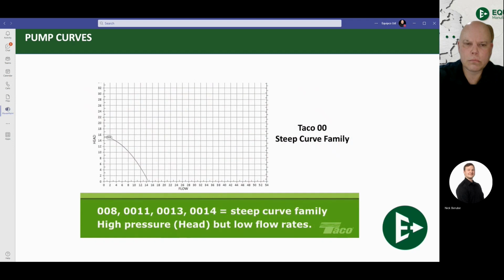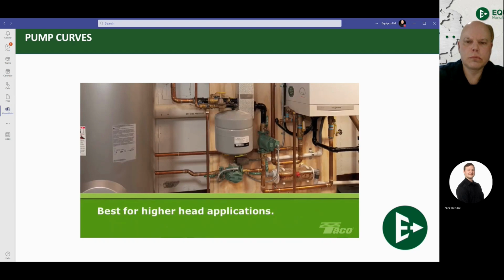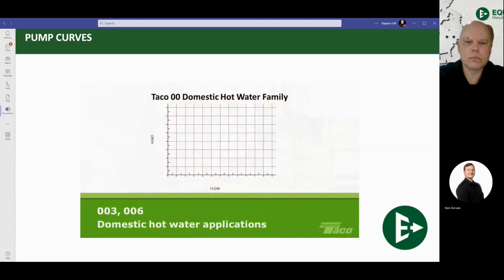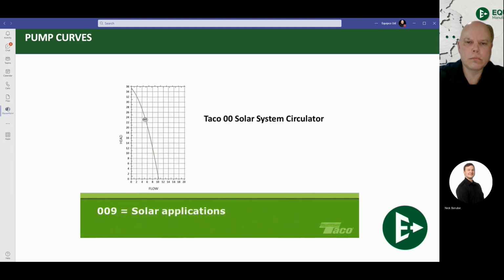On the other hand, models 008, 0011, 0013, and 0014 are all in the steep curve family. Compared to pumps with a flat curve, these circulators can generate a lot of head pressure but comparatively low flow. These circulators are best for higher head applications such as high head loss fan coils, air handlers, and heat exchangers. A third family is small but worth mentioning. It includes the 003 and 006. Both these circulators are designed for domestic hot water applications. That leaves the 009, which is in a family of its own. This pump is specifically made for solar applications.